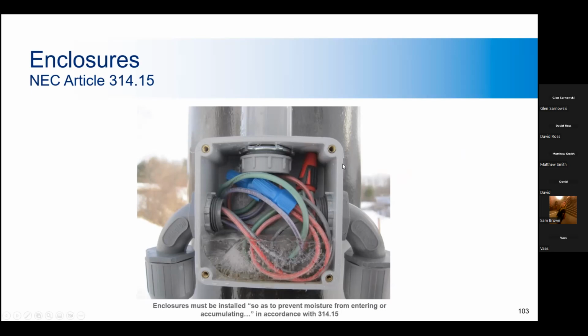So that allowed water to get into this, and you obviously don't want water in your electrical system. But since they did this inspection in the winter, the water had frozen, and you can see that it pooled in the enclosure, and it just built up until it was able to go down one of these conduits, which obviously you do not want to have in your system. You don't want water in your electrical system at all.